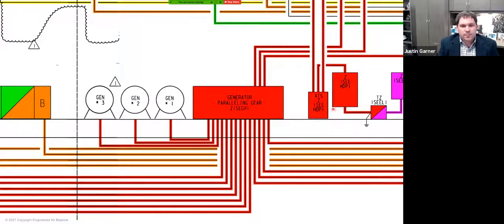And you'll see here, and I'm going to show you another picture later on, this is an automatic transfer switch. These are the workhorses of these types of systems. This particular ATS is fed by two emergency sources, as noted by the red feeders coming in, and then obviously it has a distribution feeder going out to this distribution panel here. You're going to see some of the other ones I'm going to show you will actually be fed by a normal source and an emergency source. And that's more likely what you would see in a typical commercial facility with emergency power.